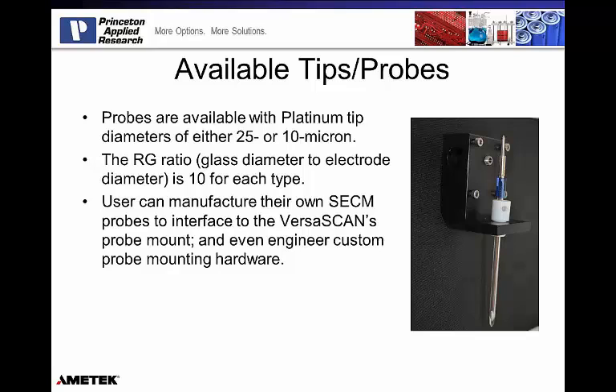When you're discussing SECM probes and SECM tips, you're going to come across a key parameter called RG ratio. It's the ratio between the glass diameter and electrode diameter for the probe itself. So for example, if we took an RG ratio of 10, when we look at the very tip of the SECM probe, if it is a 25 micron probe, that defines the diameter of the platinum disc at the bottom of the probe. So that's a 25 micron disc at the bottom of the probe, and an RG ratio of 10 means that we have 10 times that amount of glass on either side. So it would be a 250 micron diameter glass, polished flush at the bottom, and then within that 250 micron glass at the bottom of the probe, a 25 micron platinum disc exists in the middle of that.